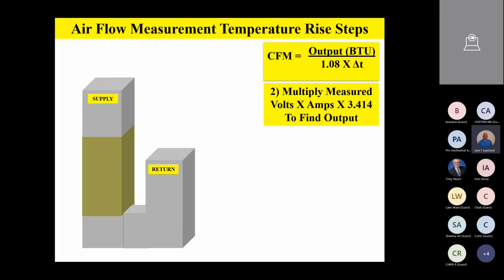Step number two, you're going to multiply the measured voltage times amperage. Now this is huge. You're going to measure with the fan running and the heat strips running, with the outdoor unit off. You're going to measure the voltage and the amperage, and you're going to multiply volts times amps times 3.414. That 3.414 is a mathematical constant to convert wattage into BTUs. So volts times amps equals watts, times 3.414 equals BTUs, and that gives you the output portion of that formula. So volts times amps times 3.414 equals the output of the unit. Write that down or remember it.